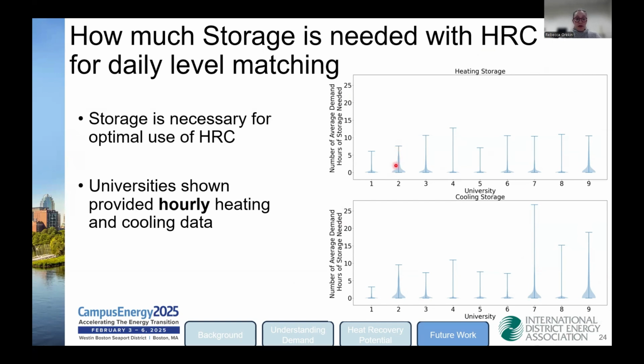These plots show distribution density. The wider the shaded area, the more of your data falls within that range. You can see that most of your data is well below 2 hours of storage, with a couple of hours in the day needing higher amounts, but most optimally you'd use your heat recovery chiller with about 2 hours of storage.